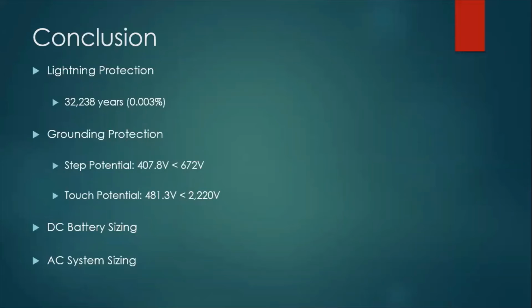All studies performed followed the proper IEEE standards to ensure the safety and reliability of the overall substation's design. The lightning protection was found to have a penetrating stroke every 32,238 years, or 0.003% chance that lightning will strike yard equipment. The grounding study had both simulated touch and step potentials below the maximum allowable voltage. The fall semester physical layout achieved a space-efficient layout that was configurable to future expansion. The DC batteries are able to operate for the minimum 8 hours if power is lost to the substation, and all AC substation loads can be serviced at any time of the year with redundant protection built in.